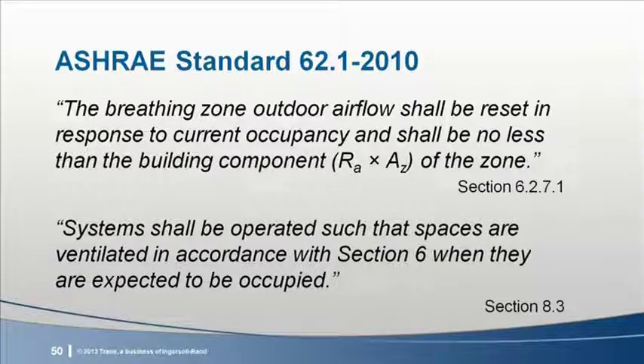Section 8 clarifies that this applies whenever that zone is expected to be occupied. That is, the standard is not requiring you to deliver this building component of the ventilation rate 24 hours a day, 7 days a week. Rather, it only requires it during the normally scheduled occupied period.